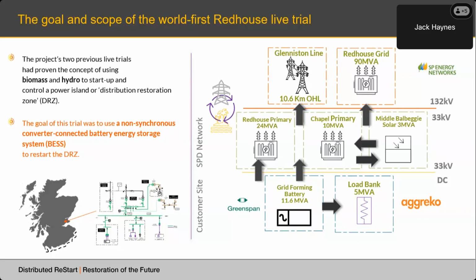We utilised a 5 MVA load bank that was supplied by Aggreko, and the purpose of this was to mimic primary demand coming on and off during the series of tests, because we didn't want to affect any genuine customers, and thankfully we didn't experience any outages during the trial period.